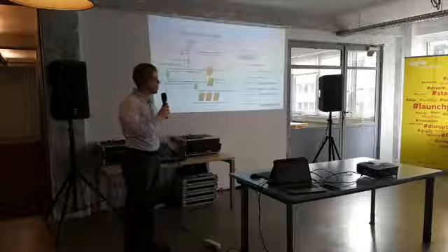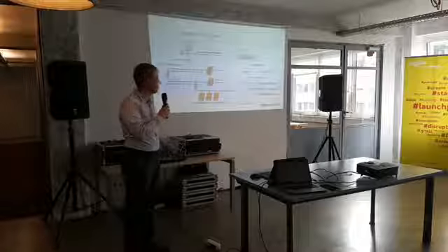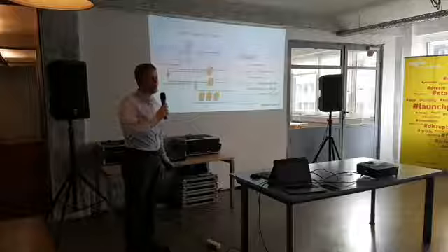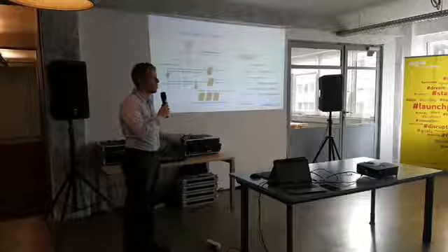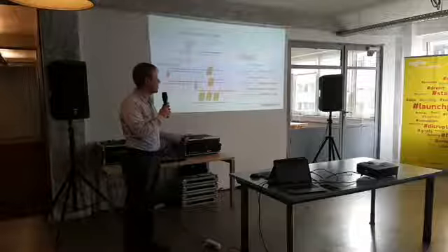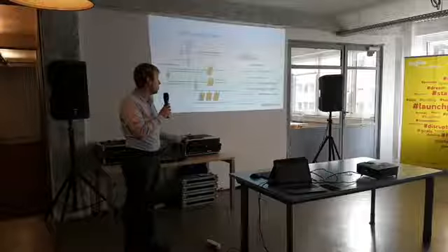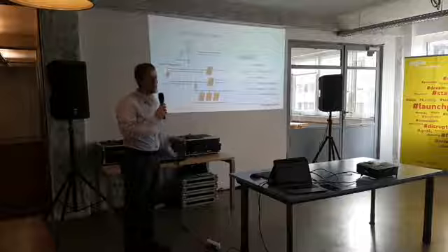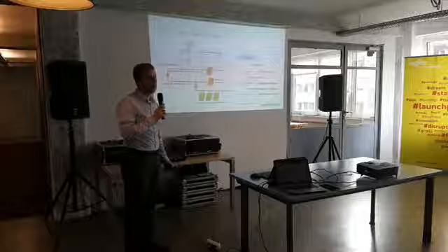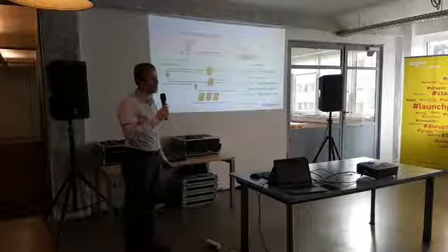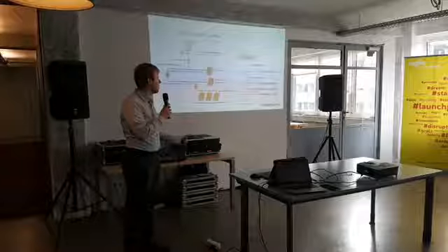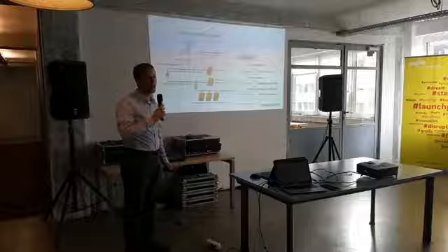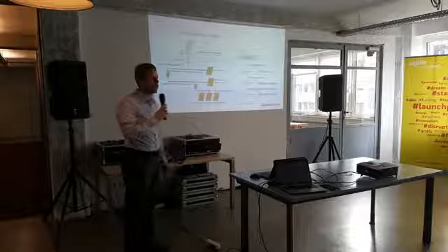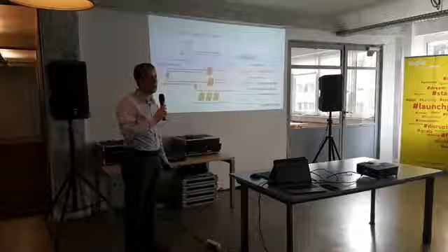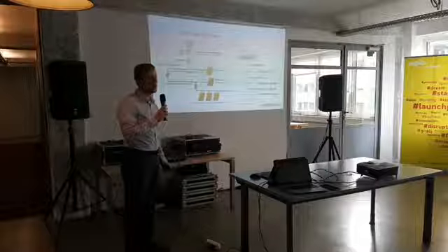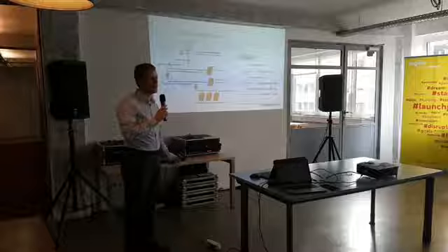And again, transformer stations, 44,000 transformer stations, transforming down to local grid, 230, respectively 400 volts. And as you can see, 9,000 kilometers high voltage grid, 46,000 kilometers medium voltage grid, it's already sometimes more, and 100,000 kilometers low voltage grid with 44,000 transformer stations. As you can see, the numbers are increasingly high as you go down the voltage, and that's where the biggest problems begin, because as you can imagine, in the high voltage level, everything is measured and can be operated from remote, whereas in the medium voltage level, that gets increasingly difficult. There are only some points in the network that can be operated from remote. In all other cases, a grid operator has to drive there and operate the switch.